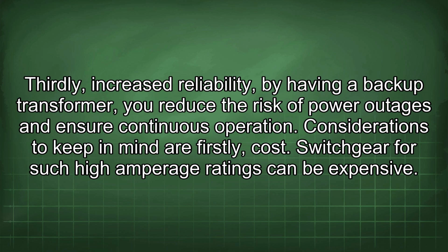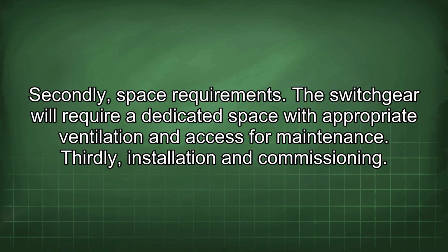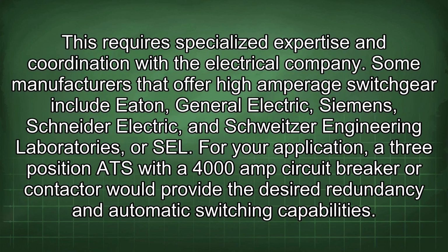Considerations to keep in mind are firstly cost. Switchgear for such high amperage ratings can be expensive. Secondly, space requirements. The switchgear will require a dedicated space with appropriate ventilation and access for maintenance. Thirdly, installation and commissioning. This requires specialized expertise and coordination with the electrical company.